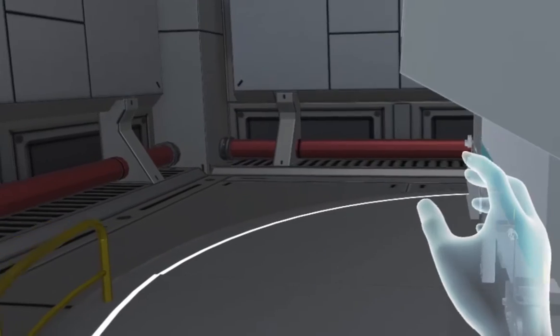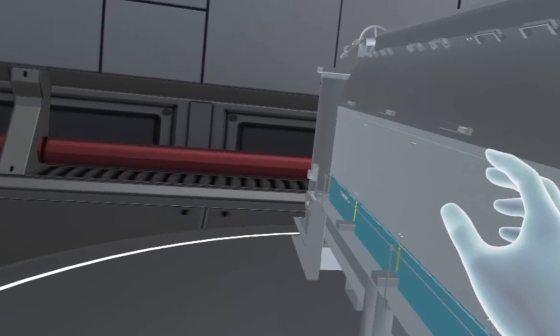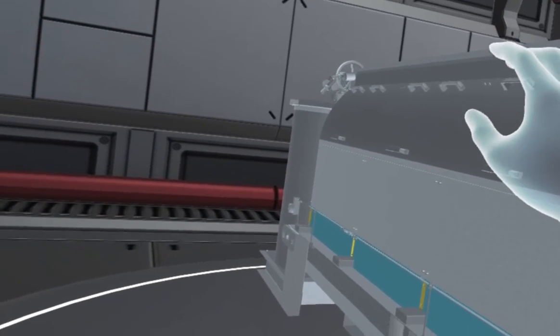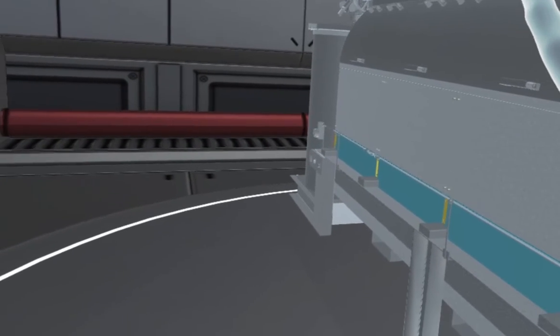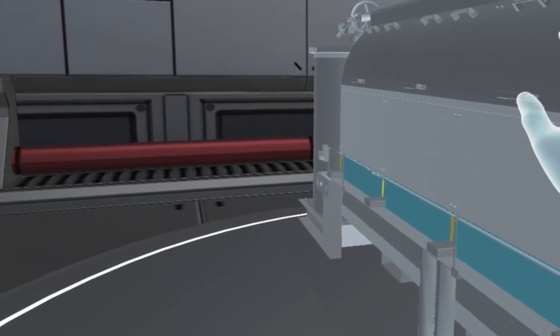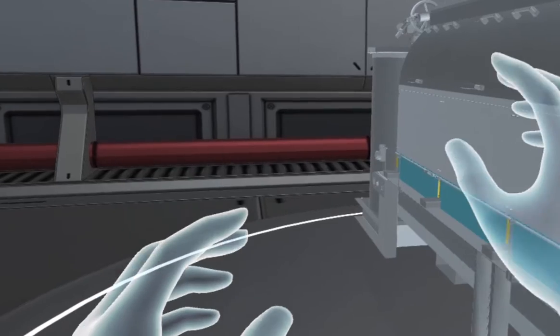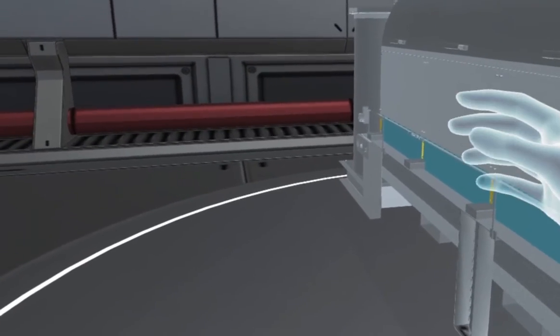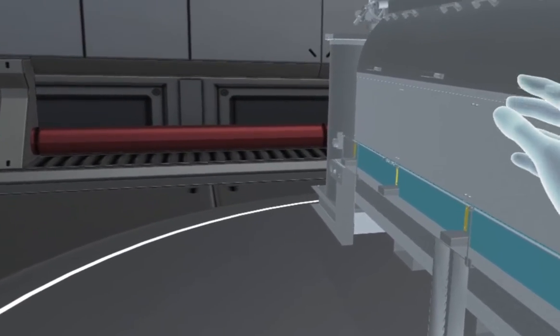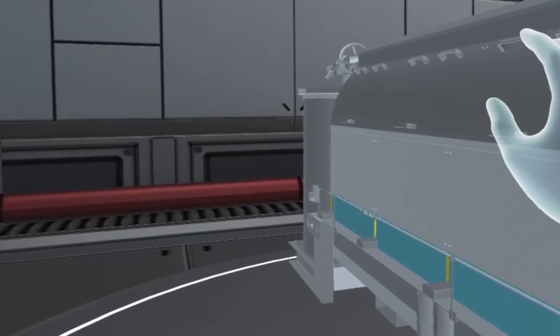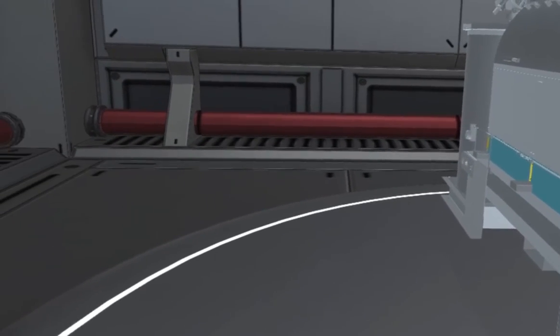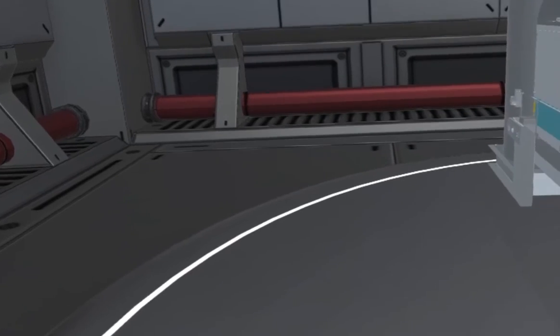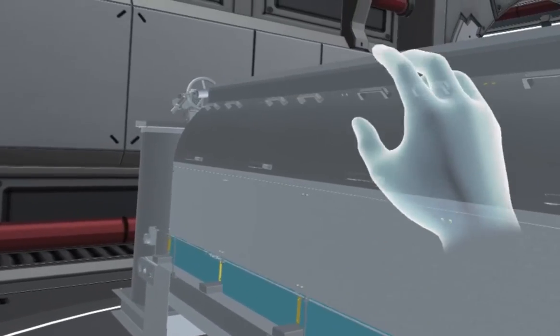So, now let's head over to the side of the unit, because we want to talk about the spray header. Now, one thing that we mentioned was blinding. Blinding is an issue for RDTs. If there's ever a time where the polymer dose is too high, it can clog a lot of the openings in the screening material and cause blinding. So, you want it to always be very clean. The cleaner it is, the more open area, the more water release, the more efficiency, and the lower the polymer usage.